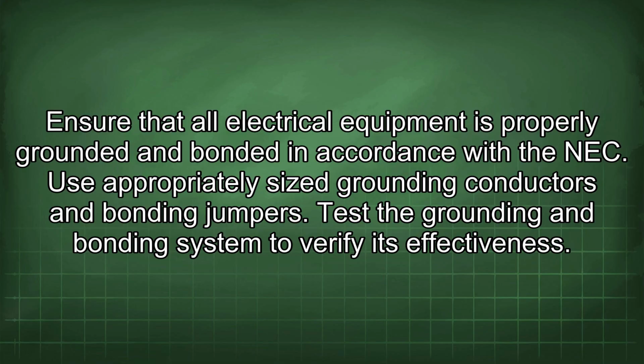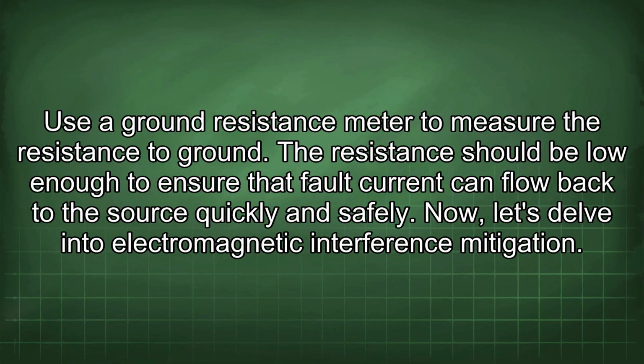Test the grounding and bonding system to verify its effectiveness. Use a ground resistance meter to measure the resistance to ground. The resistance should be low enough to ensure that fault current can flow back to the source quickly and safely. Now, let's delve into electromagnetic interference mitigation.